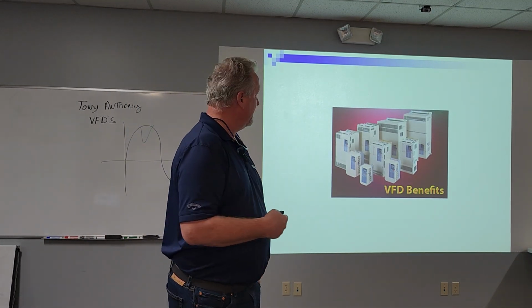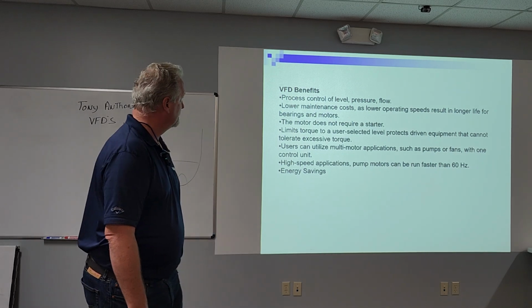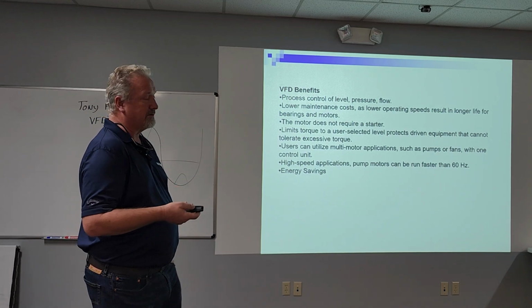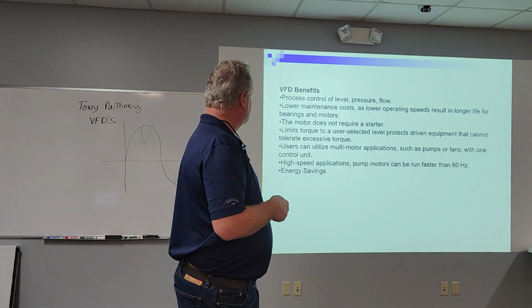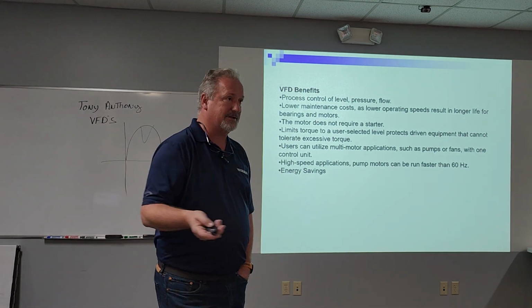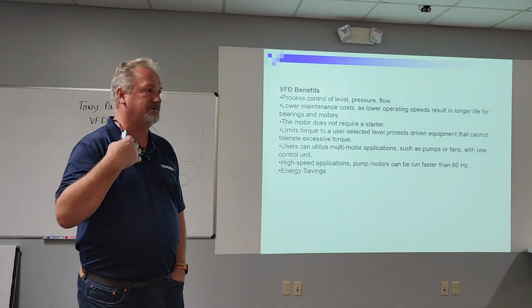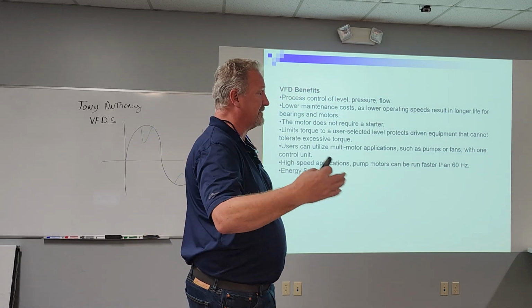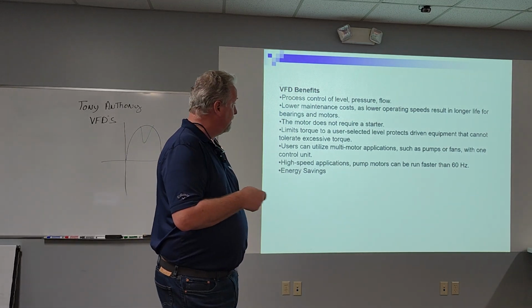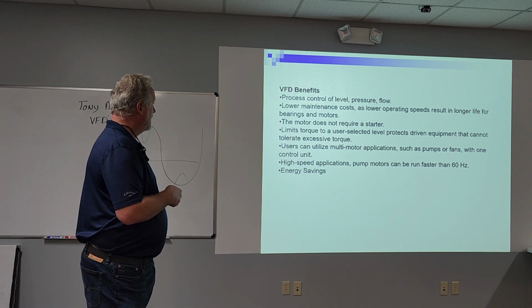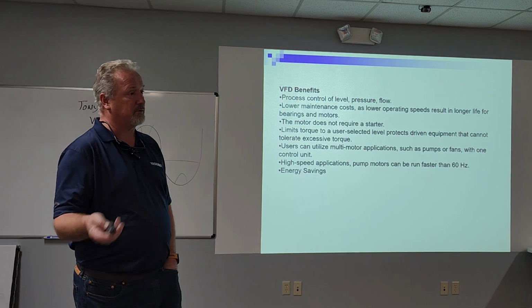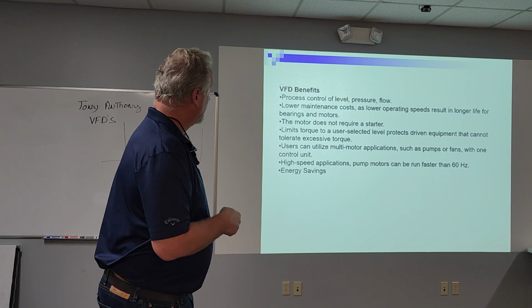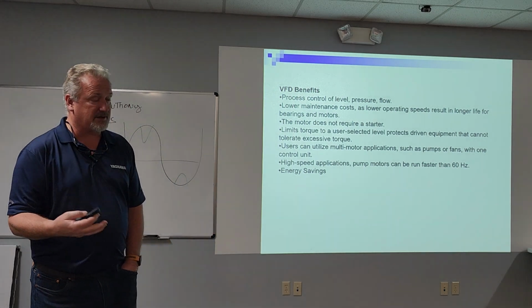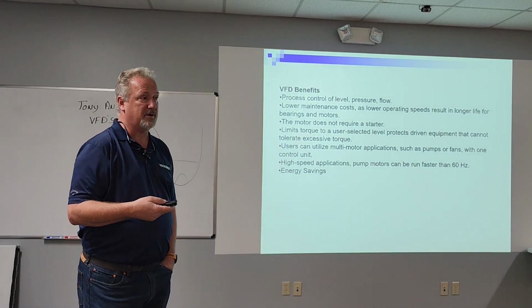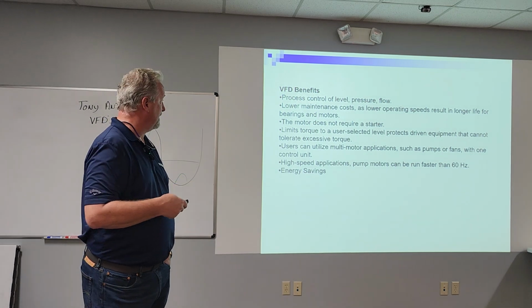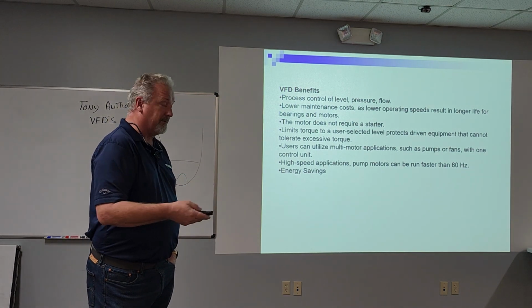Real quick, we'll go through a few of the benefits of why we have VFDs. We use them for process, level control, pressure, flow, some of the things we've just been talking about. We can lower maintenance costs, as we talked about earlier, because you're not hitting those loads from 0 to 60 hertz right away. It's better for belt life, bearings, motors. We don't need a across-the-line starter, so you don't have to worry about peak loading. You can set drives up to limit the torque, so if you're worried about over-torquing something, you can set a torque limit on the drive. We can run multiple motors from a drive.